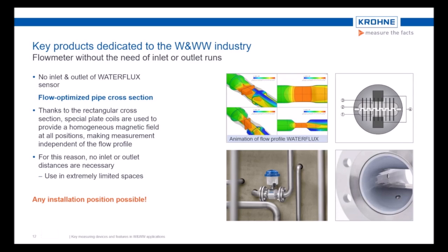The unique pipe cross section acts as a kind of Venturi pipe, what you can see on the colored pictures on the left-hand side. After a 90-degree bend, we have so many different colors which display different flow velocities, but within the measuring tube where the signal is grabbed, we have a homogeneous flow profile available which guarantees the most accurate measuring result. Therefore, we do not have any restrictions concerning the installation position of this key flow meter.